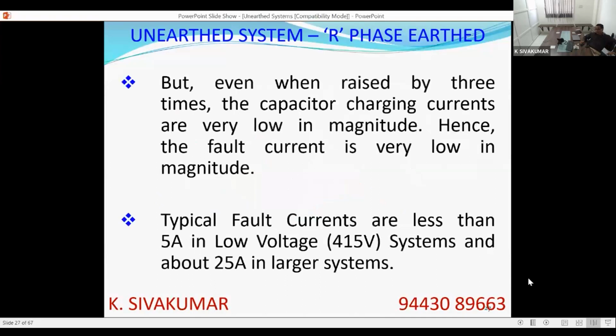Now, you need not worry, even when raised by 3 times, the capacitor currents are still very low in magnitude. So the fault current is very low. Typical values in 415 volt systems are about 5 ampere. In an unearthed system, the capacitive discharge fault current will be 5 ampere. And in 11 kV and higher systems, it is typically about 25 ampere only.